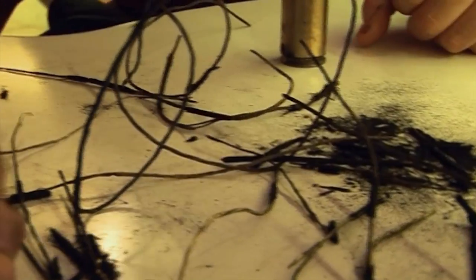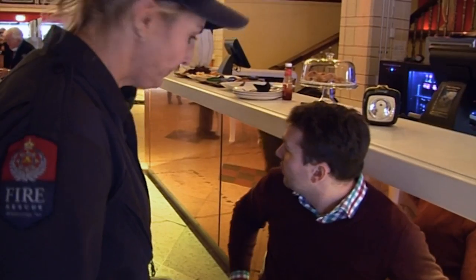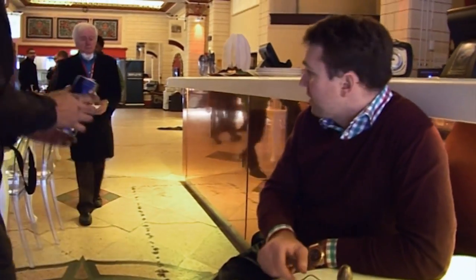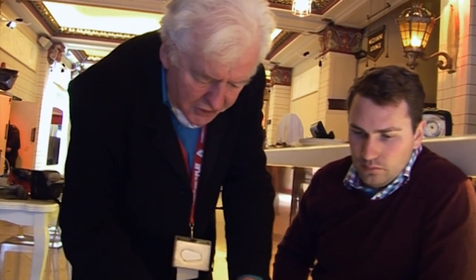How old is this cable — can you age it? Oh, this is really old cable. It was all through metal conduit, but the problem is the metal conduit had broken. It's so old that... This stuff was inside the conduit but the conduit had broken, and it's beaded like this — you've got melted bits on the ends. So it's probably old rubber insulation that's come literally at the end of its life, but it's only happened where the metal conduit is broken. So this is a really slow-burning fire.